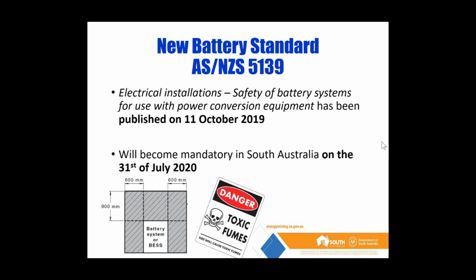Now, in the standard, it talks a lot about clearances and where you can and can't put your battery. And that's generally about it. However, you do need to know it because we are going to start enforcing it. A lot of your battery solar installations will still have to adhere to 4777 and 5033. But if you are doing batteries, you really need to get this standard in your hands, and you probably should start using it now as well, because we will be on the warpath enforcing what the standard requires in about a month's time.